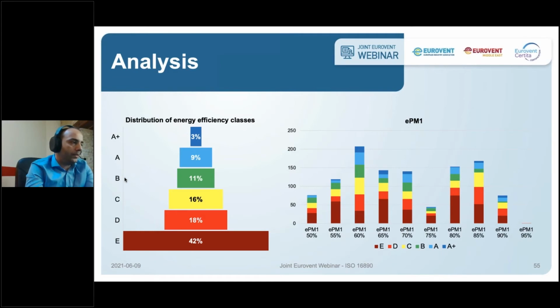If you look for a B-class filter, you're looking at the top 25-30% of air filters. If you're looking for an A-class filter, it's around the top 12%. So you can use this table to define your requirement in terms of energy efficiency. On the right side you see an example for EPM1 filters, the distribution of different air filters in terms of energy classes A+ to E, and filter efficiency from EPM1 50% to EPM1 90%.